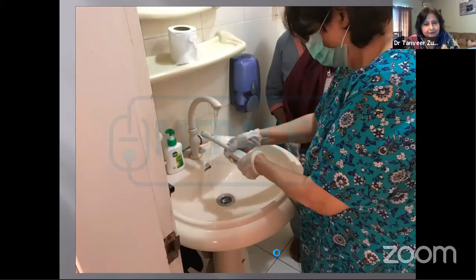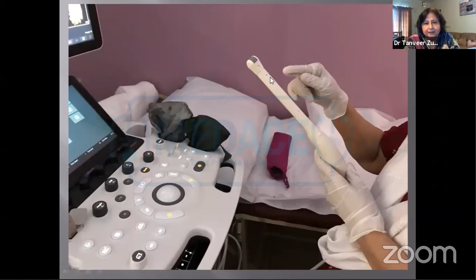Before starting work in the morning, the probe should be disconnected and cleaned under running tap water with soap, thoroughly. And there are some grooves here in the probe, and these grooves are for the attachment for the interventional procedure. These grooves should be cleaned very carefully. If you just wash it and clean it with a cloth, it will not reach there.